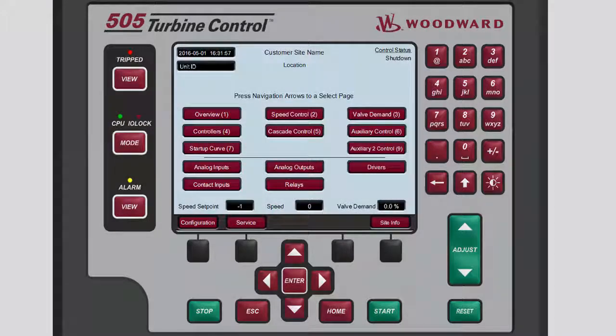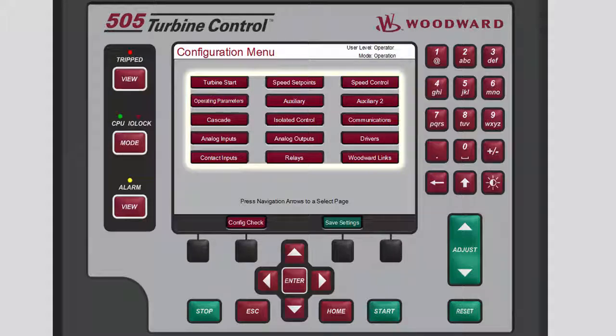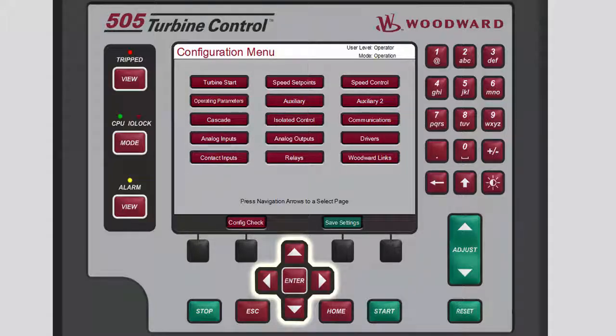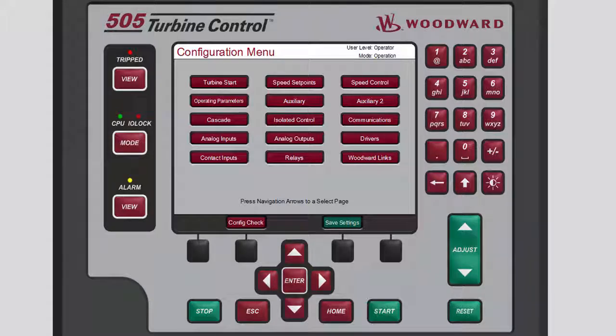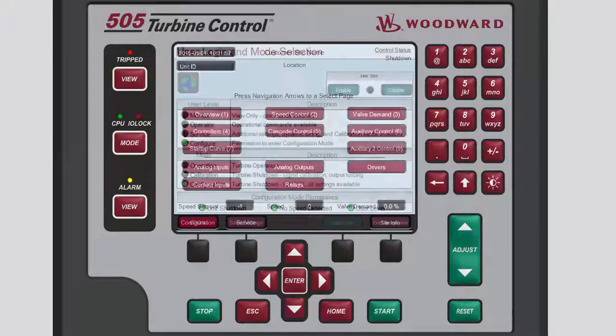Now we'll show you how to access the Configuration Menu and the Service Menu screens. To open the Configuration Menu from the Home screen, press the black Function key below Configuration. The Configuration Menu contains navigation buttons to all of the features and options of the 505. To select any of these buttons, use the navigation cross keys to highlight the applicable button, then press Enter. To make changes from the Configuration Menu, you must be logged in at the Configure User Level and the Unit must be placed in Configuration Mode. These functions are described in detail in the Changing User Levels and Changing Modes and Languages tutorials.